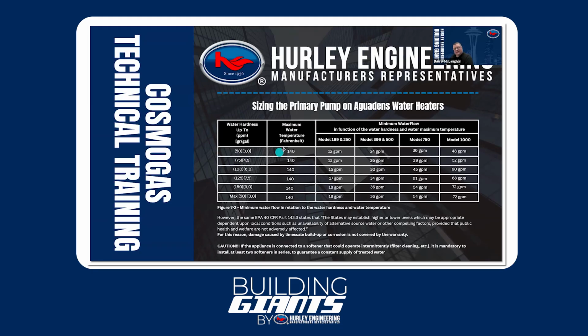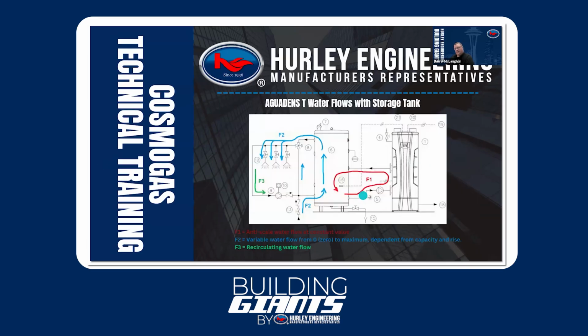So the second line is going to be maximum water temperature at that hardness. And then the third line is going to be the recommended flow that you should have for that boiler at that hardness and temperature level. So you can see, and we're going to pick one out here and do an example in just a minute, but if I were to say I have 100 ppm or 6 grains of water hardness and I'm running at 140, then on the 750, I should have at least 45 gallons of flow through my boiler. And when I say that, let me step back for 1 second here. That applies to this F1 circuit only. So that 45 gallon minimum is going to be for F1.